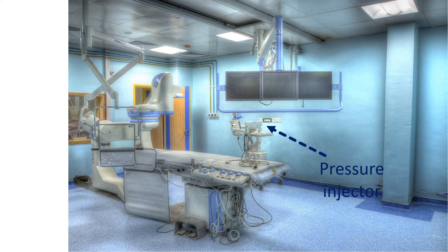A pressure injector is used to inject radio contrast for left ventriculography and aortography at graded speed which is adjustable as per need. Infusion pumps, resuscitation tray, medication tray, and racks for catheters and devices are other things not shown in this image. When electrophysiology procedures are done, an electrophysiology recorder, stimulator and ablator are additionally needed. Other devices for interventional cardiology procedures include intravascular ultrasound console and optical coherence imaging console. A portable echo machine is also at hand when needed, and some procedures require transesophageal echocardiography as well.